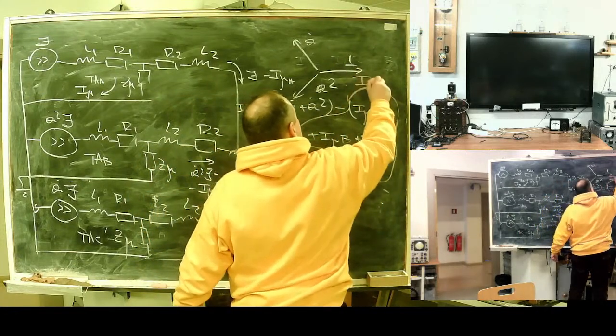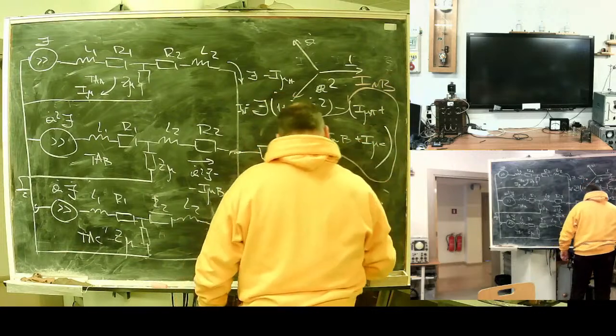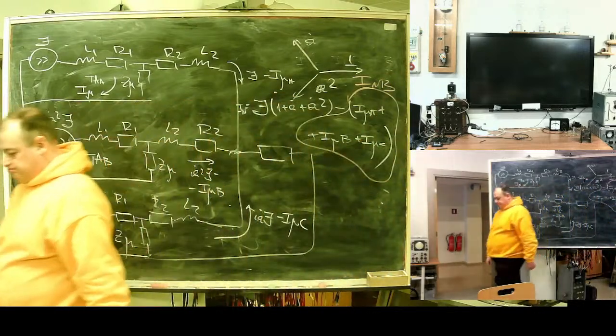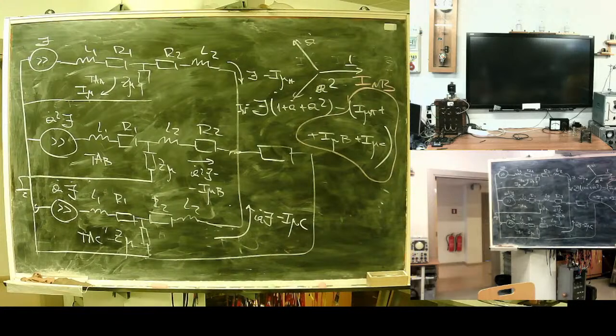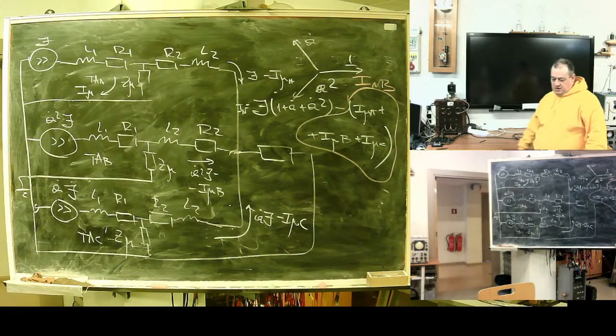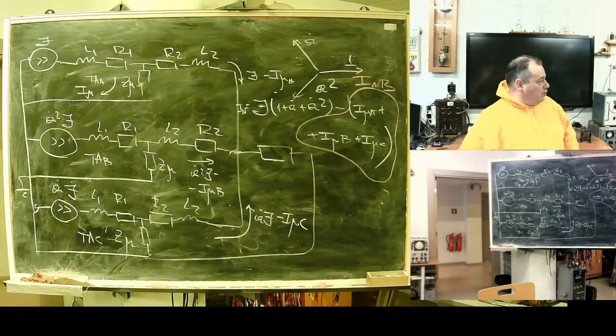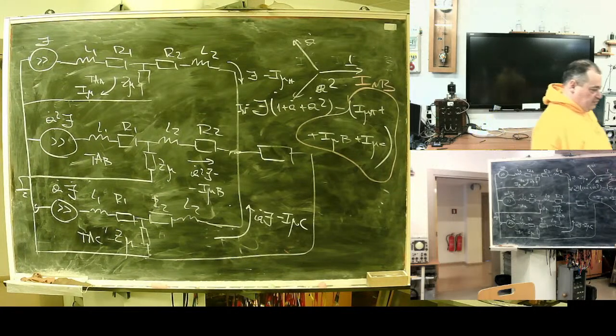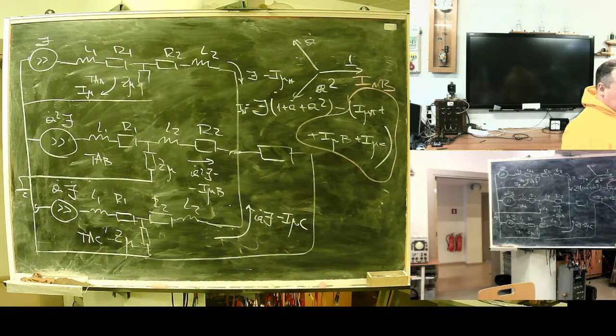So in case of symmetrical load, this will fall. It's called the non-balanced current of the Holmgren scheme. If we would use an ideal transformer, this current should be 0. In reality, even with sequential numbers, you take one model, same model, not only same rating, same batch of production, transformers with sequential numbers. Anyway, there will be a difference.